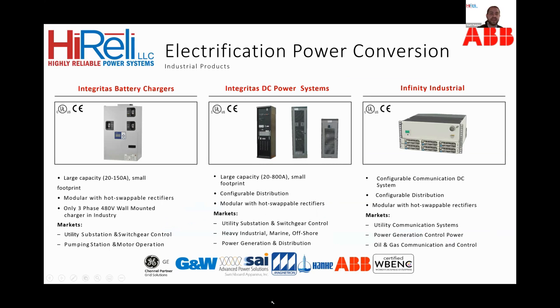Reviewing ABB's Integritas family of battery chargers, starting with the left, the Integritas battery charger, which is for all your wall-mounted applications, such as small utility substations and control houses. You have the Integritas DC power systems, which is your large floor-mounted rack unit for the larger utility substations and power generation facilities. And then on the right, the Infinity Industrial is for rack-mounted applications such as telecom and communication systems. Each of these products uses switch mode rectifier, or SMR, technology, which gives you an efficiency between 94 to 97%, all the way down to 10% of your load.